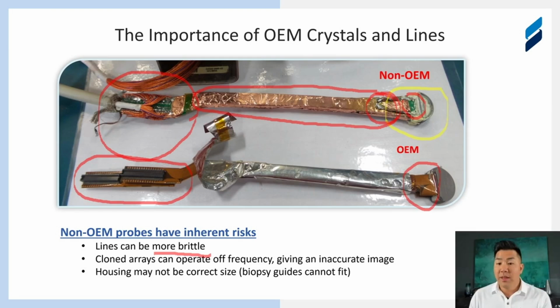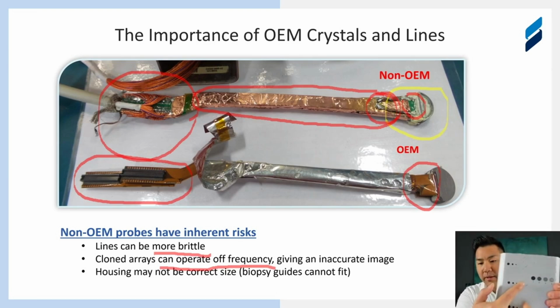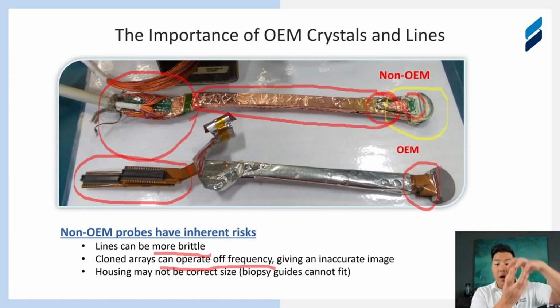Now, you look at the non-OEM crystals. These crystals can operate off frequency and give an inaccurate image. There have been cases where you're scanning a phantom, and if you look at some of the targets, let's look at this circle, that circle can actually look slightly oblong, and it's not a perfect circle. So it's operating off frequency. Either the sender or receiver, we're not sure, but something is wrong, and it's just not a risk that we're willing to take for our customers whom we support.